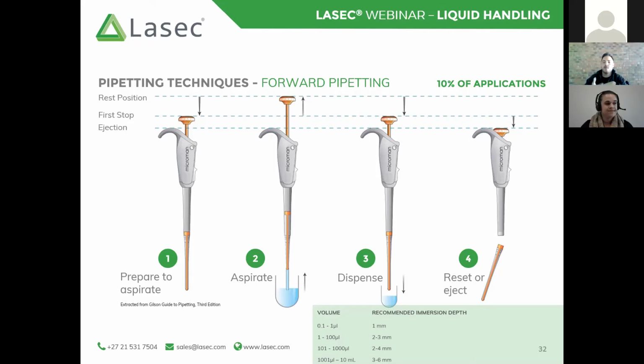So with the pipetting techniques being continued, we are now going to talk about your positive displacement technique and the forward pipetting technique that's employed here. The reason it's a forward technique is that the whole purpose of a positive displacement pipette is also to eliminate the need for reverse pipetting. So again, it's going to cover about 10% of your applications, those really difficult, tricky samples that you struggle with pipetting with an air displacement pipette.